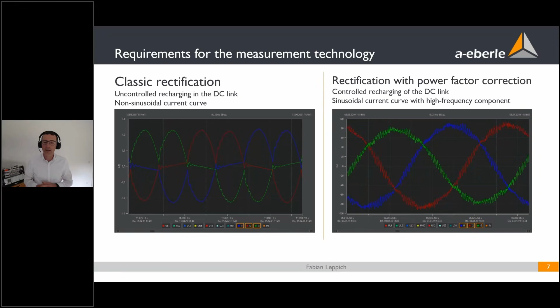These threshold values could only be controlled with technologies that can measure these so-called supraharmonics. So we have, for example, wind farms from 2 until 9 kilohertz which can only be recorded and controlled with a new technology of measurements, and all our devices - PQI LV for the low voltage grid, PQI-DA Smart, as well as PQI-DE - can have this functionality. So new technologies in the grid, new prosumers, new consumers have new fingerprints, and the typical switching frequency will be higher, and the measurement technology which we bring into the grid must also be able to control these higher limits due to the fact that we get more of these consumers and prosumers into the grid.